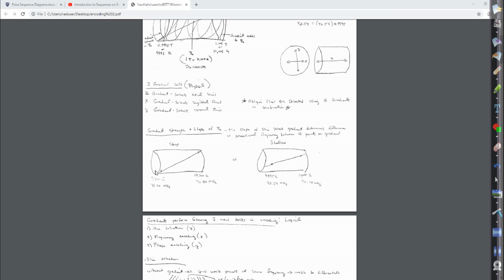And you said we get more slices? Sometimes we'd be able to get more slices. Thinner slices. But you'll definitely get thinner slices, yeah. Steeper gradient slopes are usually always associated with thinner slices, or better resolution.